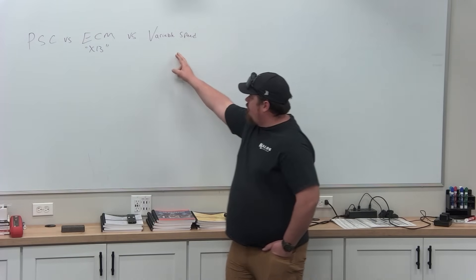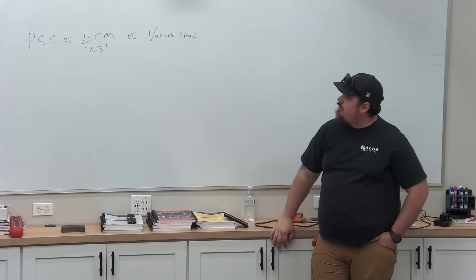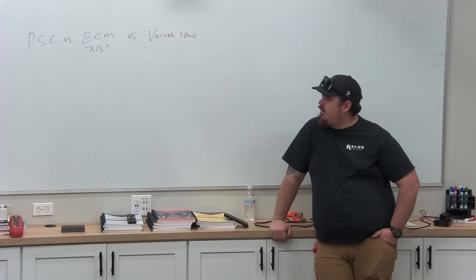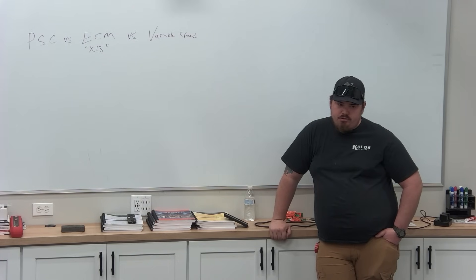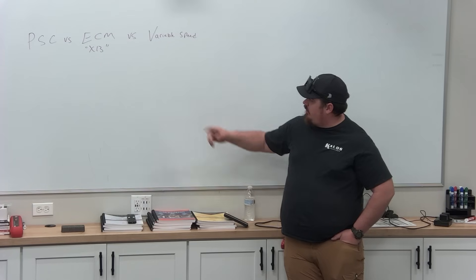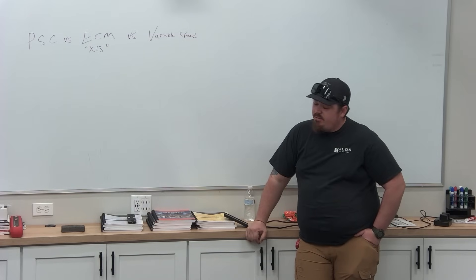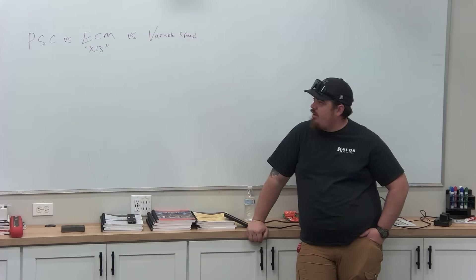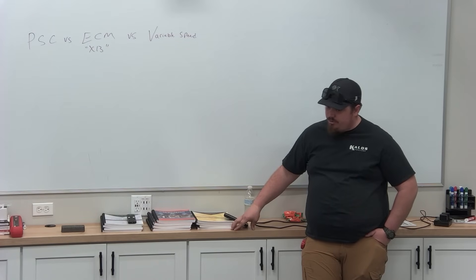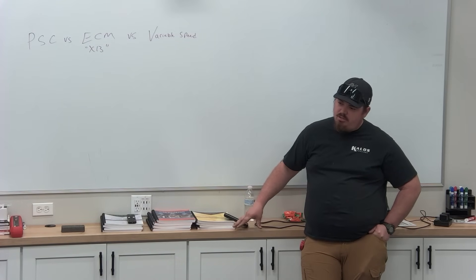ECM is the most user-friendly; variable speed requires a little more programming, but it's better at helping overcome static pressure issues. Both will perform very similarly. Longevity will be affected by static, so that's where static testing matters. We don't want to be replacing these motors — a 16-pin motor or the five-pin communicating motor for infinity or EL series systems. Out of warranty, these are over $2,000 motors. We want to make sure we're looking after the homeowner, looking after ourselves, and doing things ethically.